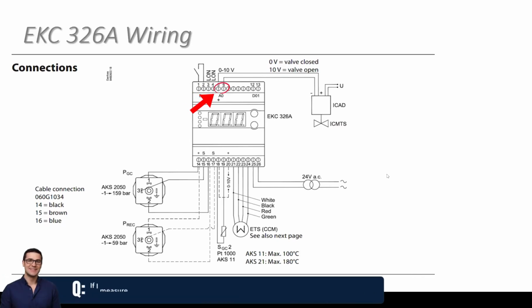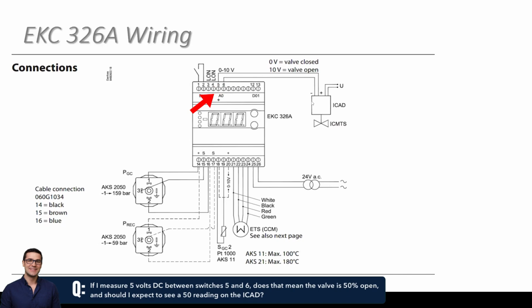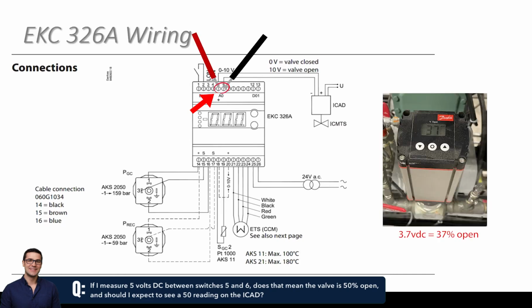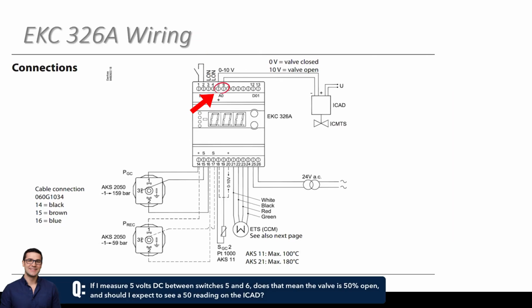And then when we go to 5 and 6, that is the valve. 0 volts is the valve closed, 10 volts is the valve open. So if I go on it with my meter to 5 to 6 and put it on DC volts and it says 5 volts DC, that means it's 50% open. So I should be able to match that up to the ICAD. So I look at the ICAD, if it says 5.0, I should be 5 volts on there, correct? Yep, and I've got a nice little ICAD handy too here, but yeah, if you can see there's a little glare there, I apologize, but there's a screen right at the top, and that should be showing that opening degree that would match on a 0 to 10 volt scale what voltage you're seeing there.